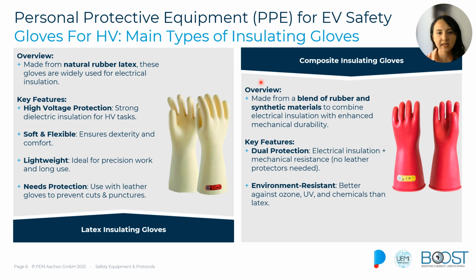On the other side, we have the composite insulating gloves. In these cases, we have blends of rubber with other synthetic materials, and the reason for having that combination is to have dual protection, electrical and mechanical protection. So the advantage of this is that often we don't need external layers of leather gloves because these gloves are already cut resistant and much more durable. Also, they are more resistant in critical environmental places, like for instance, they can be resistant to ozone, to UV, to chemicals, and so on.